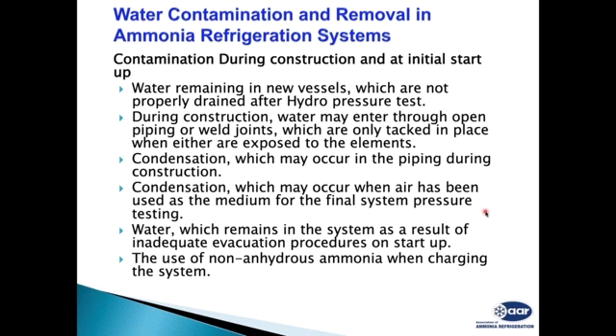Then we have condensation occurring in the pipes and other equipment lying on site, which are not clean while being installed into the plant. Condensation may occur when air is used for testing the equipment; many times people use normal atmospheric air. Along with this air, moisture will go in. Even if we vacuum and remove the air, the water which has entered with it will remain in the system.